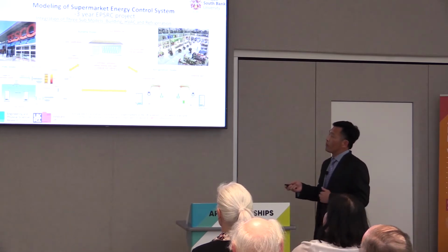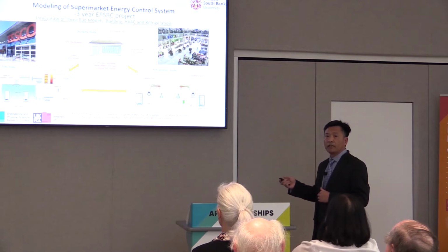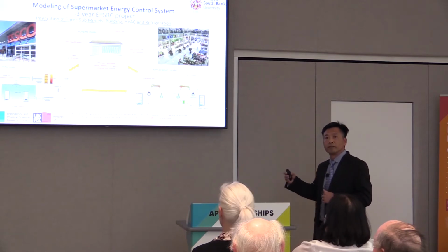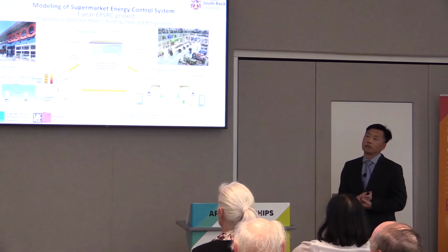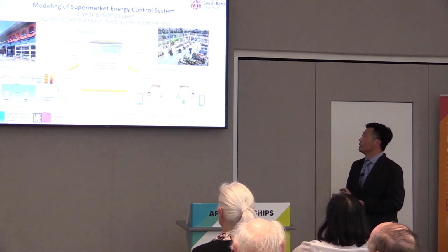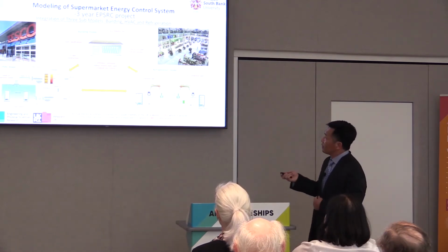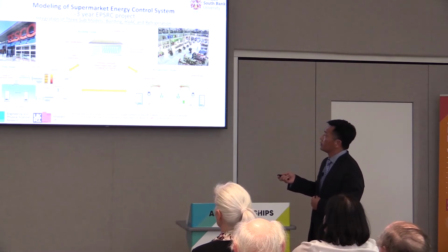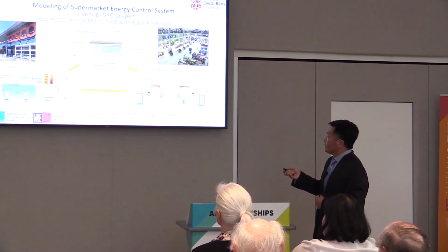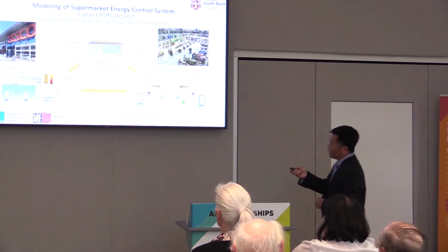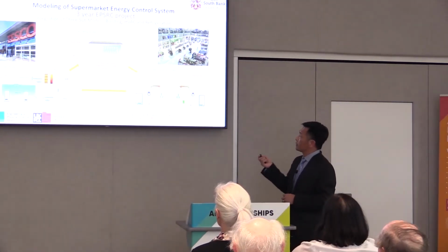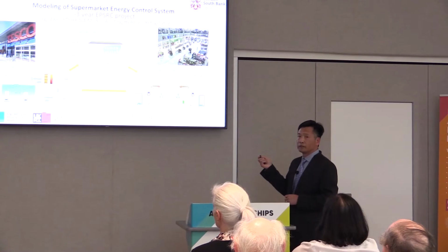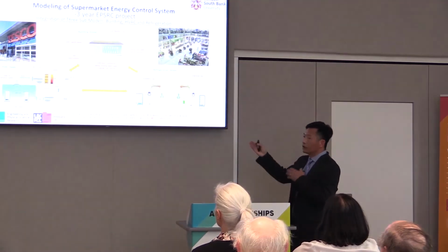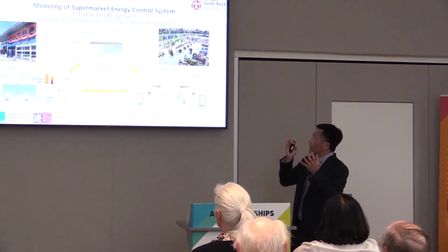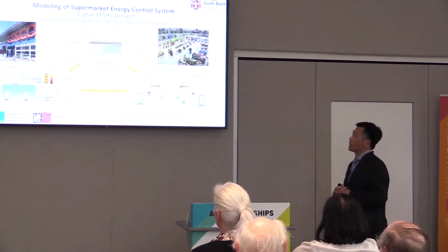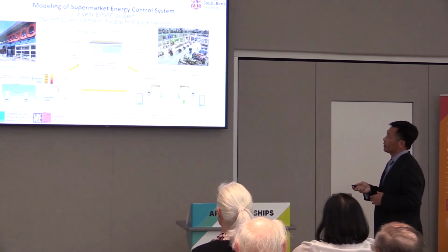So in the supermarket air conditioning system, the heating is more important. Most of the time, cooling is not needed, only heating. So you can see here, there is no cooling coil in the air handling unit, only the heating coil. The second heating coil comes from the superheat of the refrigeration system. So the refrigeration system can be integrated into the HVAC system. This is the HVAC system.